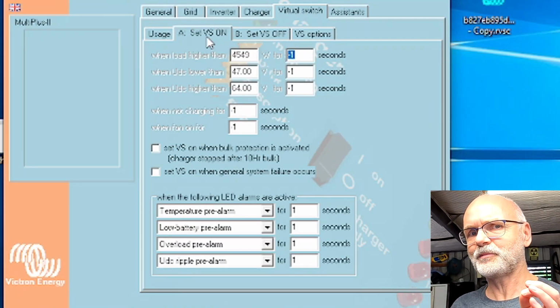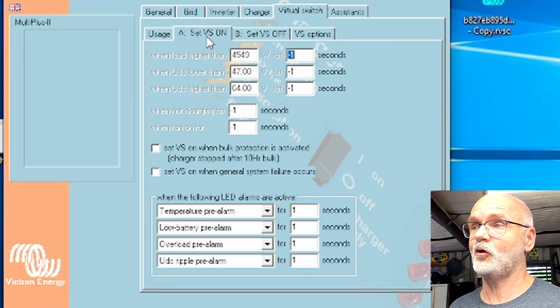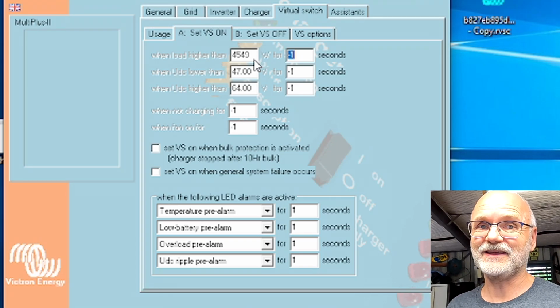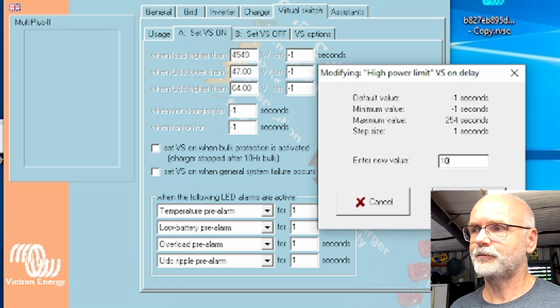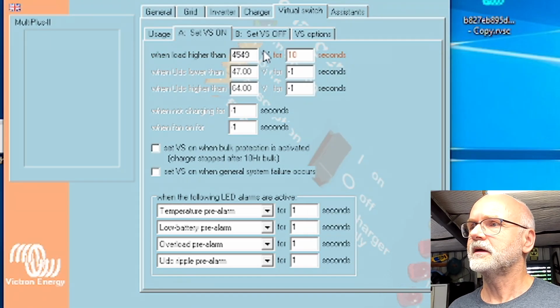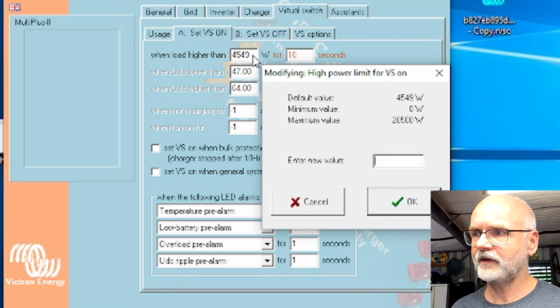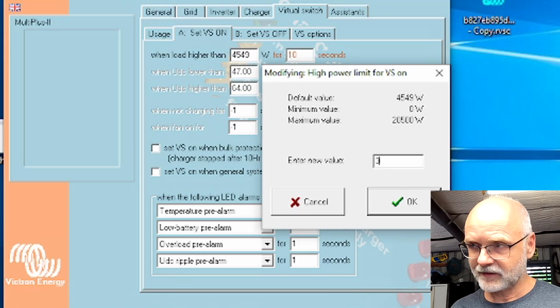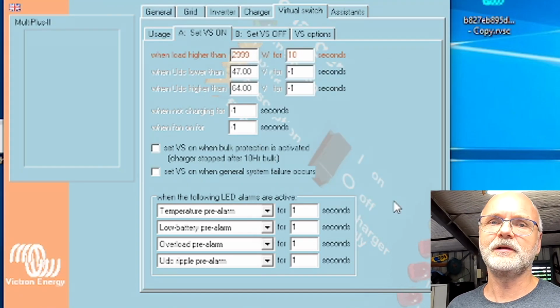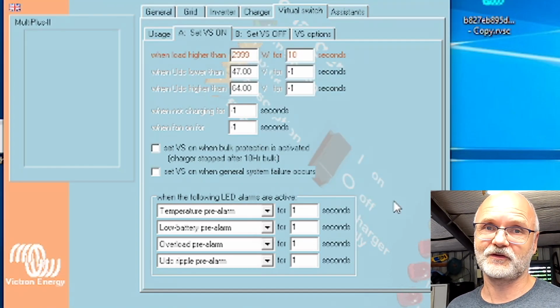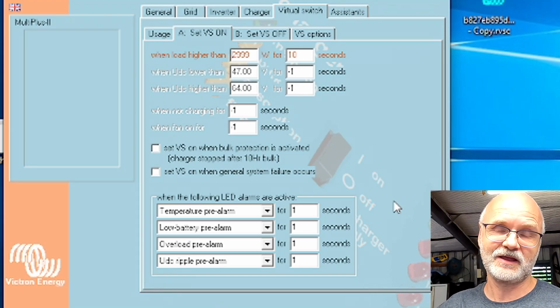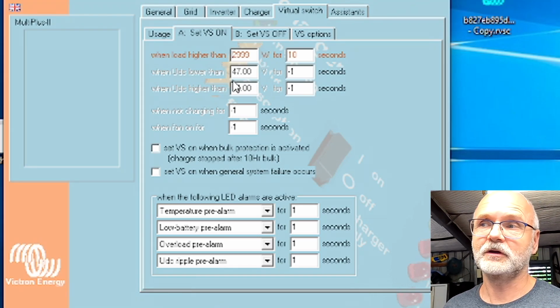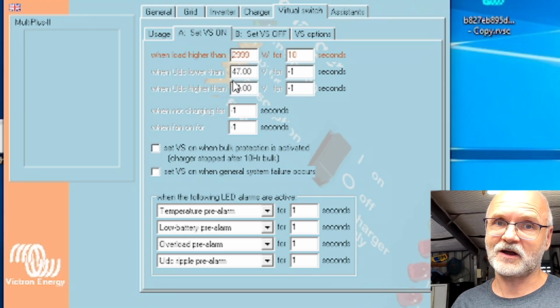And you can set certain parameters for the relay to turn on now. If the load is higher than a certain threshold, turn the relay on. So we can put 10 seconds in here, and then this field activates, and we can say if we pull more than 3000 watts from the Multiplus for 10 seconds, it will start the Phoenix as a support device. And you could do the same here for voltage levels as well. And this is for different functionalities.